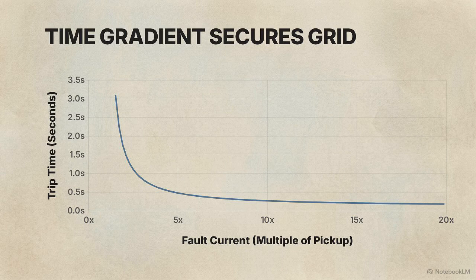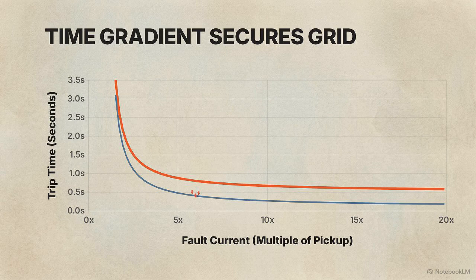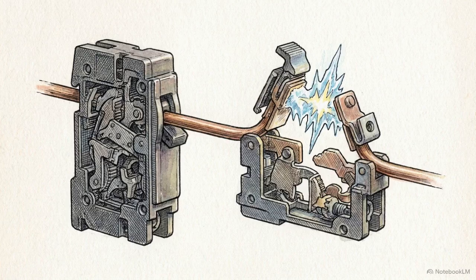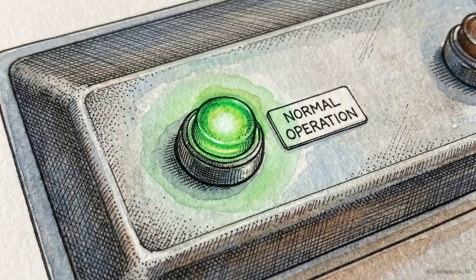We first plot the curve for a downstream feeder breaker. This establishes the baseline response time for any protective devices located further out in the local network. We then plot the transformer's primary relay curve above that downstream breaker. We intentionally configure a time multiplier setting to create a gradient of 0.3 to 0.5 seconds between the two curves at any given fault current. This delay forces the system into a cooperative sequence. It gives the downstream device a fraction of a second to clear a local fault first. The transformer relay waits, preserving power for the rest of the grid, stepping in only if the downstream breaker fails.